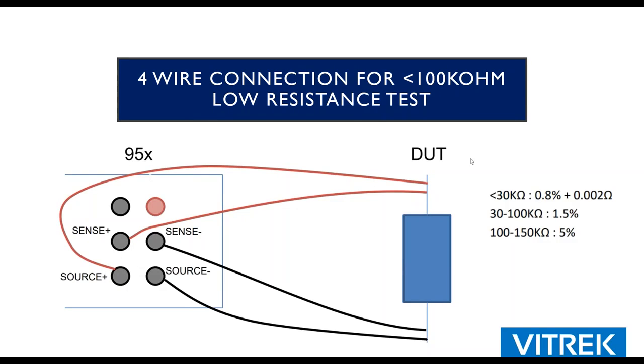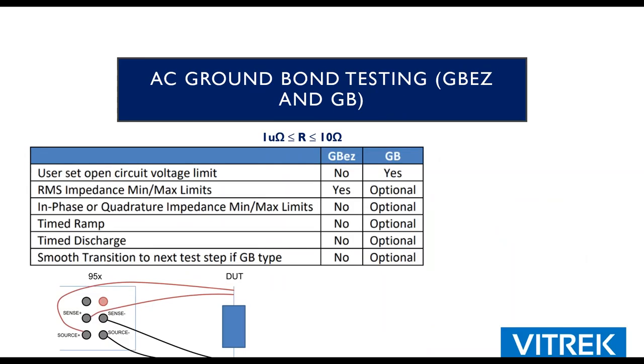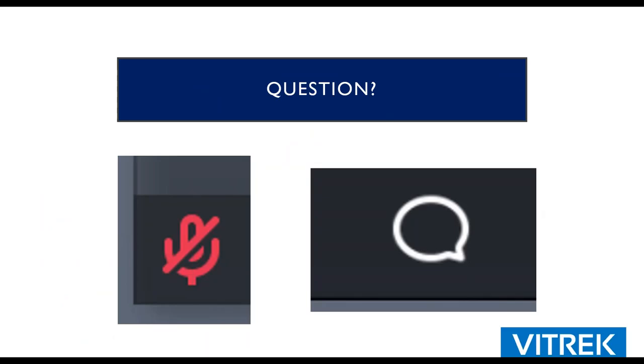This breaks down how to do a 4-wire Kelvin measurement. Again, this is important, especially with low resistance measurements, as you null out any voltage drop in the test leads automatically. When doing an AC ground bond test, you can see that we have multiple different limits that you can apply at different times, a lot like you can with our Hipot tests. This is a unique feature if you are trying to make a very precise ground bond measurement. So do you have any questions about the types before we get into workstations here?